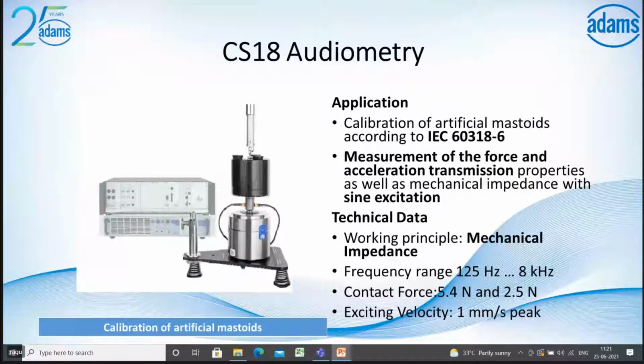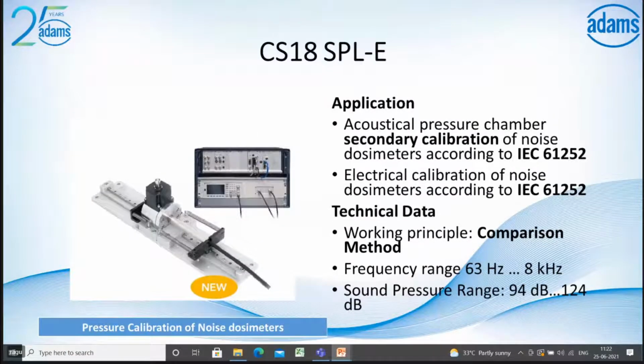And audiometry calibration. So this is for the simulator of human heads and ears. It's IEC standard 60318 for the measurement of force and acceleration transmission property by the mechanical impedance method. The frequency range you can go up to is 8 kHz, and the maximum force is 5.4 Newton at the contact force, either 5.4 or 2.5 Newton, and the excited velocity is 1 mm per second peak for the calibration of artificial mastoids. And CS18 SPLE, this is specially for the electrical calibration of noise dosimeters according to the standard IEC 61252.